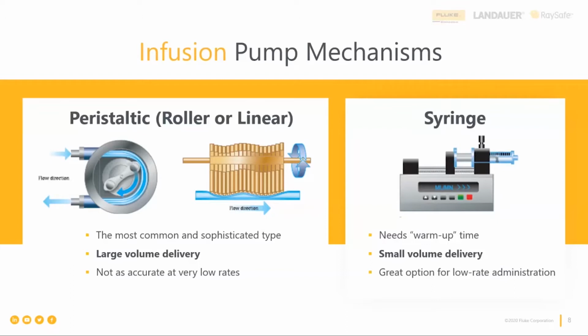Katya, there's also one more kind. It would be in the large volume delivery category here, and that is the little cassette kind that goes into some of the infusion devices, IV pumps, and they act more like an on-off valve. The peristaltic roller or linear delivery mechanisms actually are more of a continuous delivery. They don't start and stop, but this cassette is all on or all off, and it goes off, on, off, on, off, on in order to control the amount of volume that is delivered, at the cost of less smooth flow delivery. So there's that kind also.